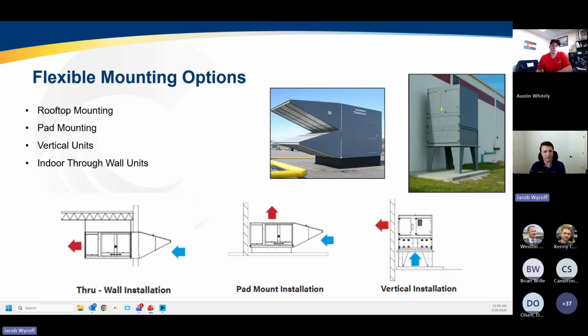Along with that, we can also offer indoor units hung from the roof in the form of indoor through-wall units or indoor under-roof units where we provide a plenum package to duct into the inlet of the unit. Because these are 100% outside air units, whenever you're mounting these units indoors, you need to make sure that you're able to supply that outside air to the inlet of the unit. And that's a key consideration you want to think of whenever you're looking at mounting these units indoors.